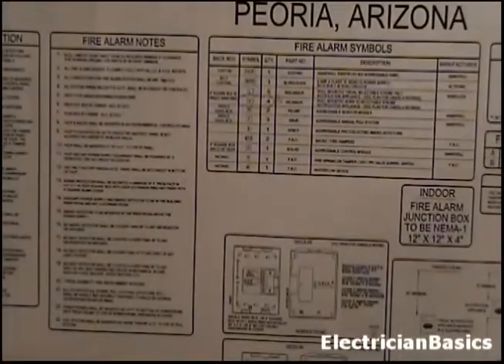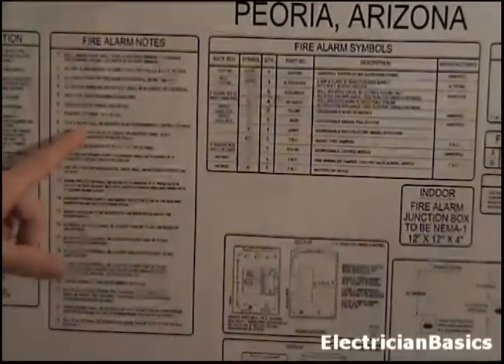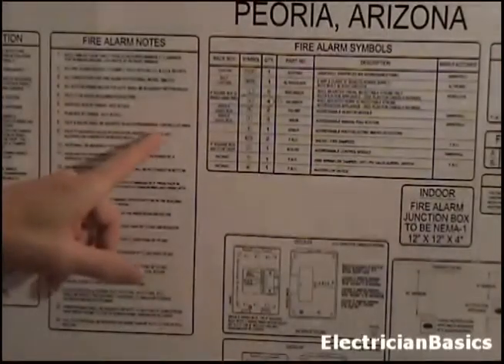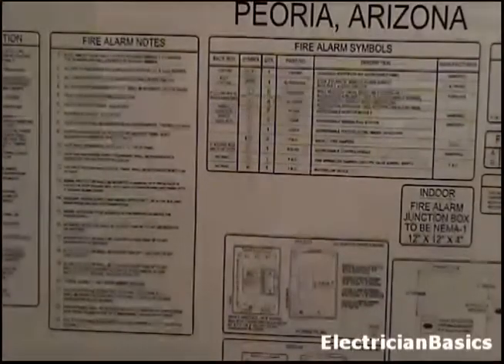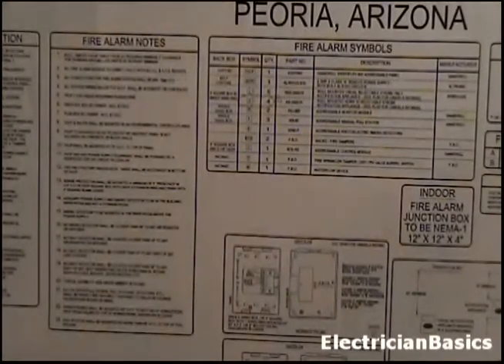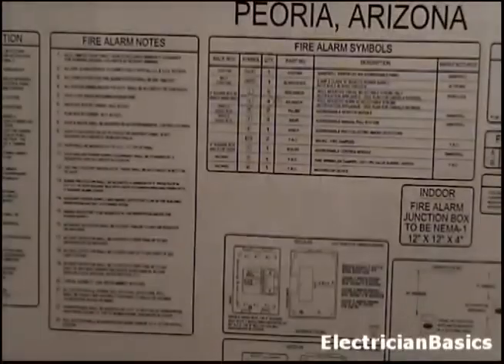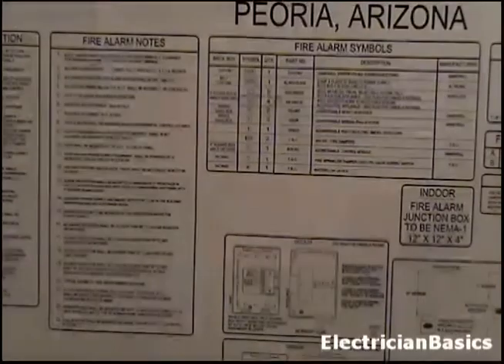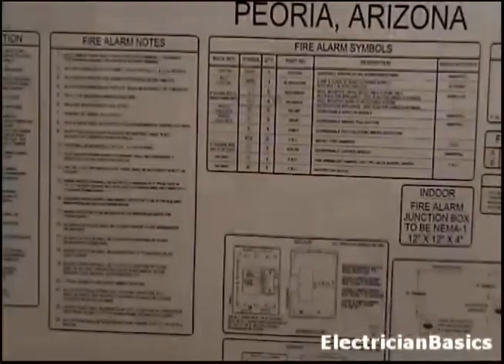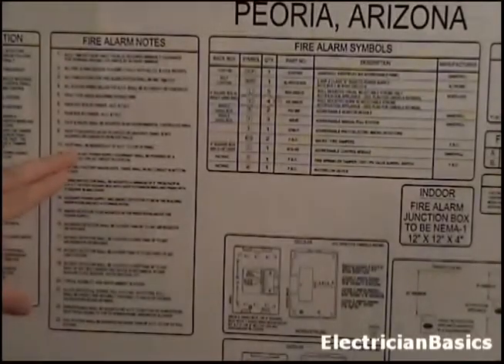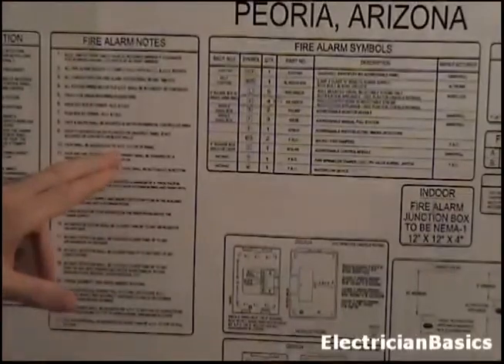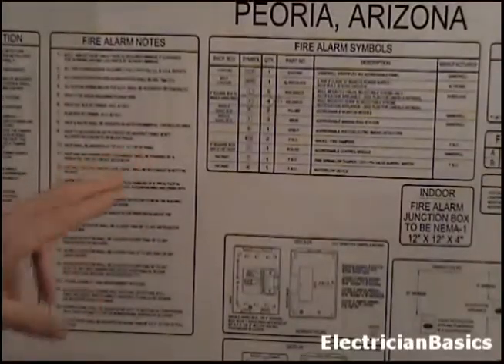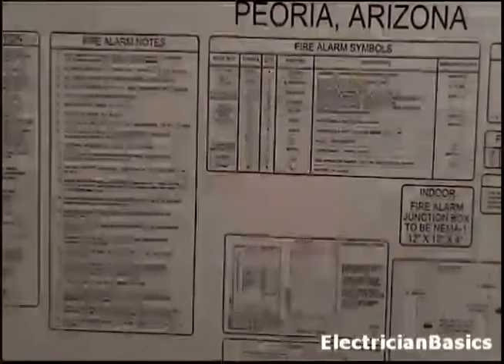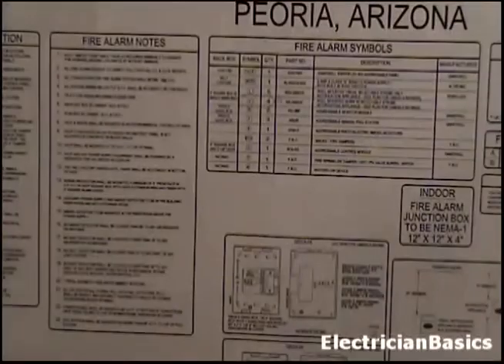Okay, FACP fire alarm control panel and NACP notification appliance circuit panel shall be mounted in an environmentally controlled area. 9. FACP to be mounted on 3/4 inch plywood or unistrut panel. Panel is not allowed on concrete or block walls. Okay, so this is giving you, when you install this, make sure you mount it on a 3/4 inch sheet of plywood. 10. FACP fire alarm control panel shall be mounted at 70 inches above finished floor to the top of the panel. So that's something you have to keep at the top of that panel, 70 inches above finished floor.